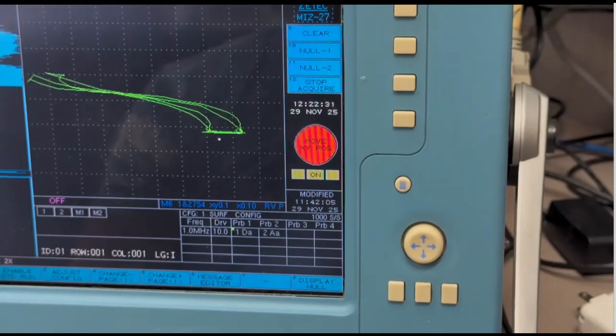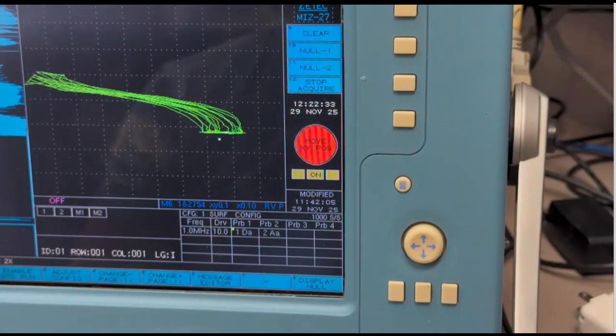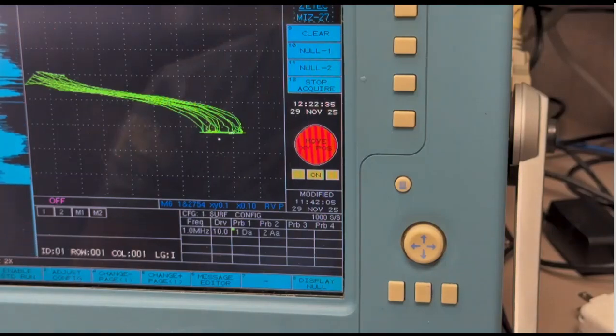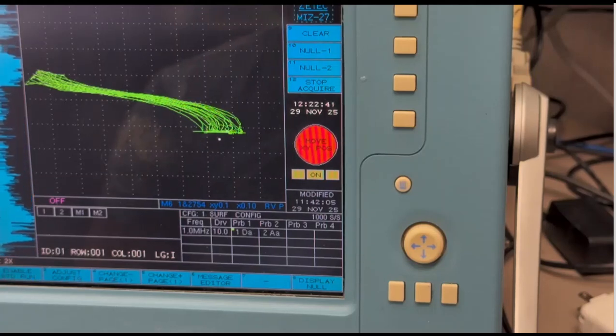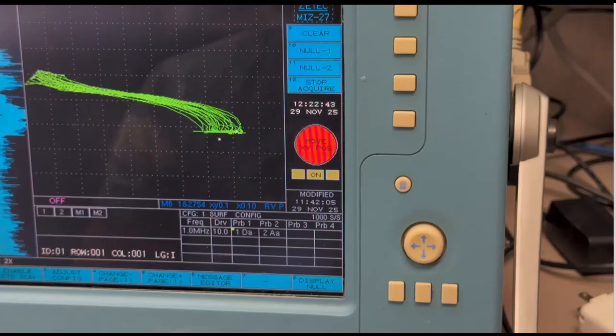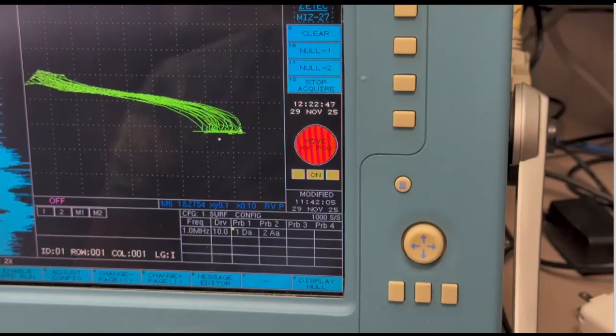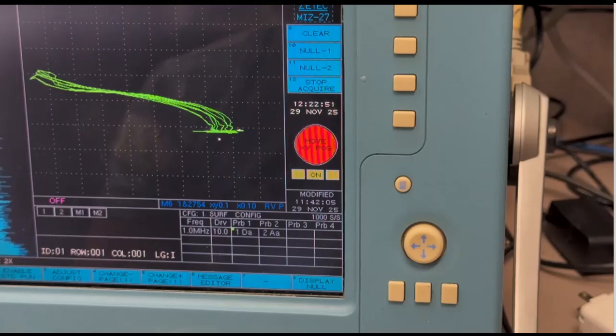I'm taking all the tinfoil off now and just go back to the surface breaking notch. Beautiful signal, right? You're not impeded by those additional layers of good material on top of the flaw. And that's really all that impedance graph is trying to show you. When you got something that's open to the surface, it's going to have low phase, big signal. And when you start going below the surface, increased phase lag because you're going deeper, smaller signal, probability of detection goes down.